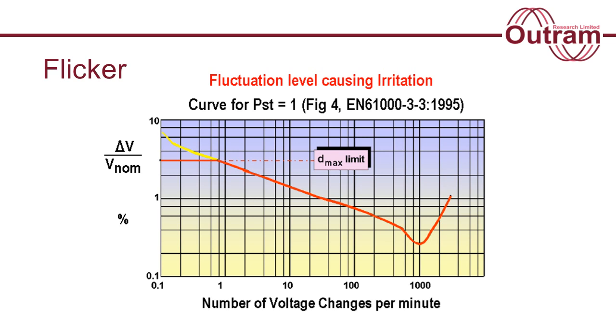So the degree of irritation we experience is very much related to the frequency of the variation that's causing the flicker. And just because a voltage is within tolerance is no guarantee of flicker-free lighting. Above about 25 Hz, we become less sensitive as the separate flickers fuse into something our eyes treat as continuous. We can be affected by higher frequencies if they can match our sensitive region.